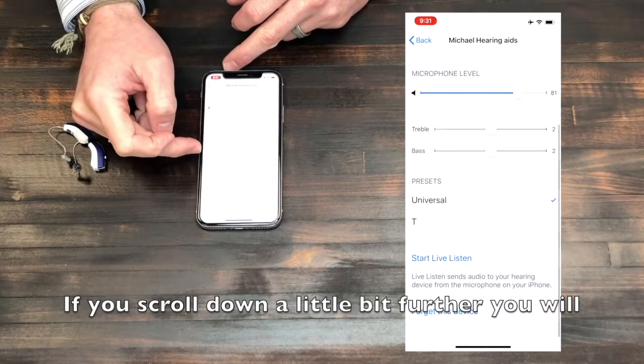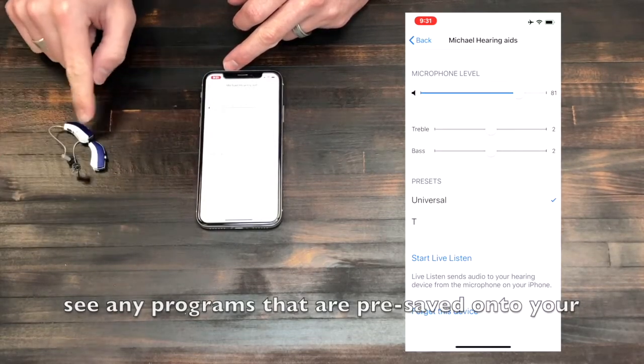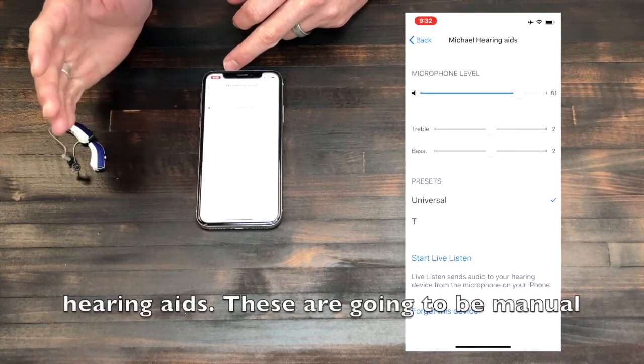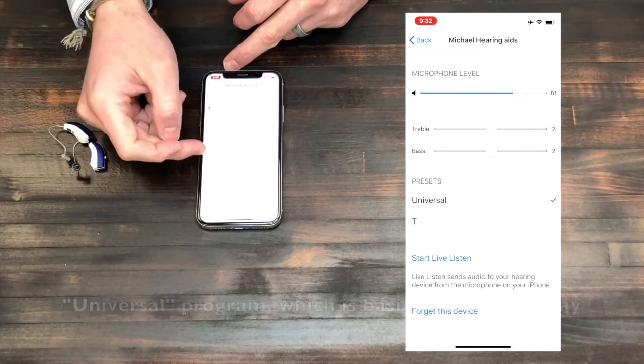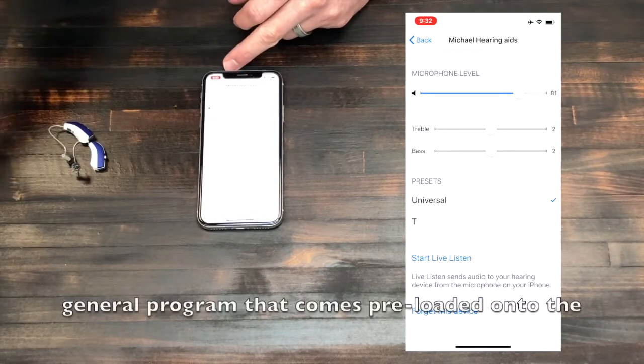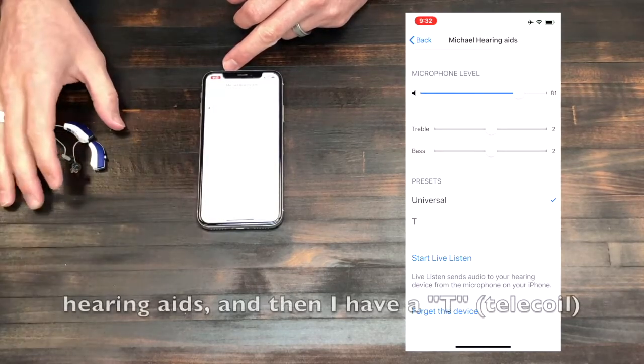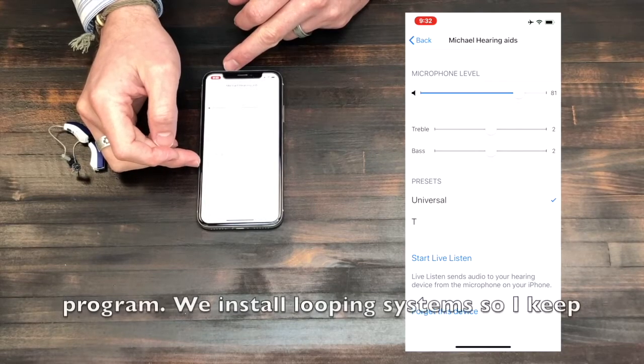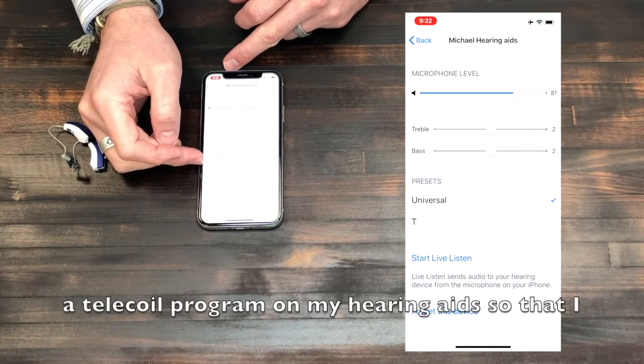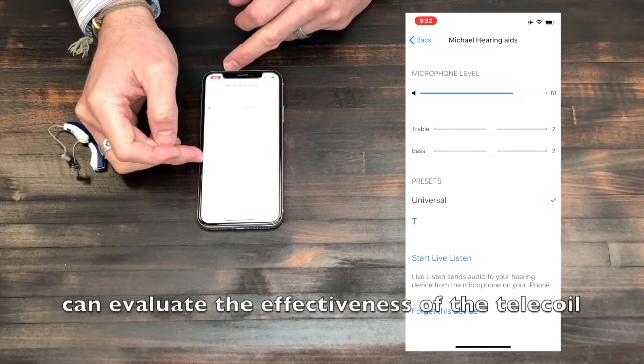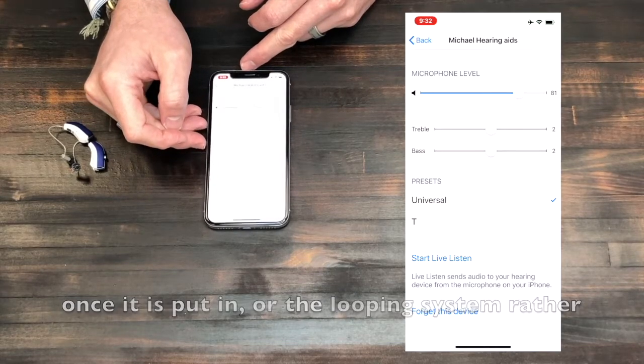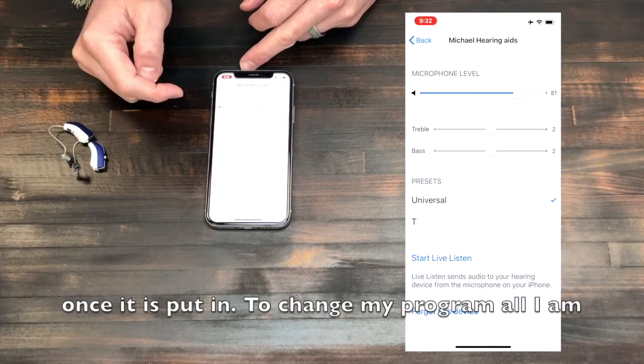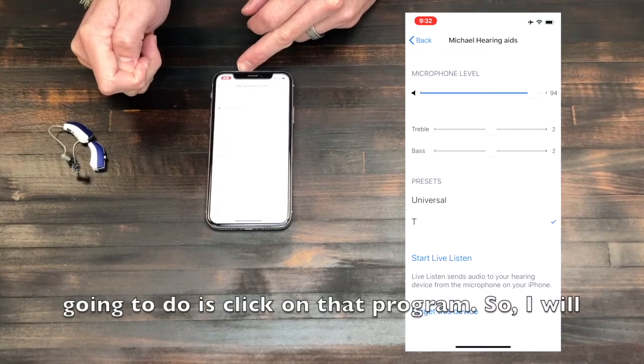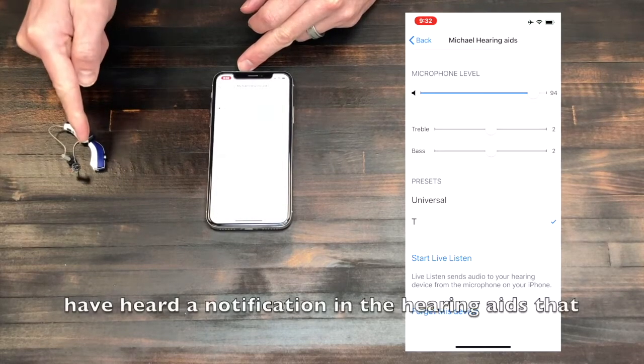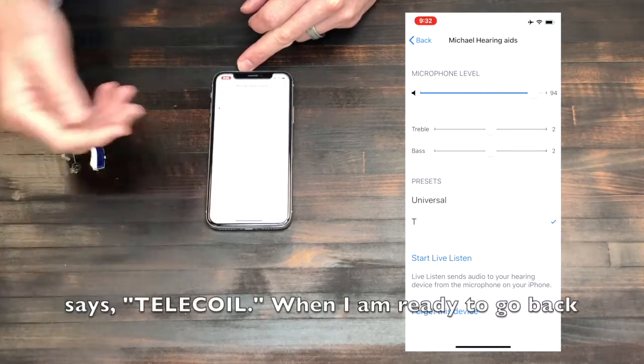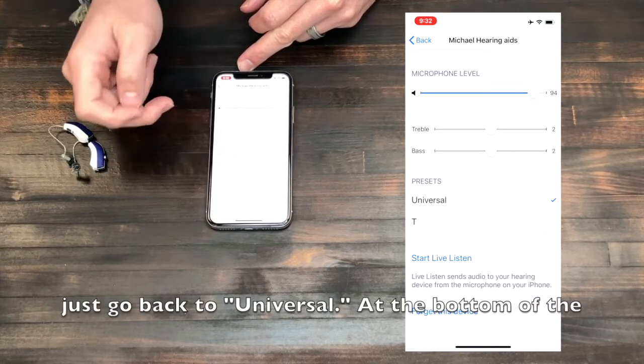If you scroll down a little bit further, you'll see any programs that are pre-saved onto your hearing aids. These are going to be manual programs. So in my hearing aids, I have a universal program, which is basically the everyday general program that comes preloaded onto the hearing aids. And then I have a telecoil program. We install looping systems, so I keep a telecoil program on my hearing aids so that I can evaluate the effectiveness of the looping system once it's put in. To change my program, all I'm going to do is click on that program. So I will have heard a notification in the hearing aids that says telecoil. And when I'm ready to go back, just go back to universal.